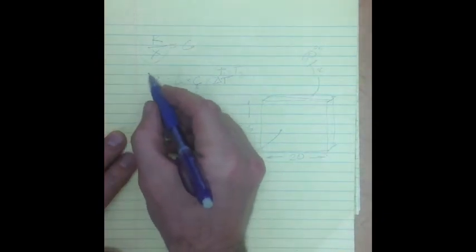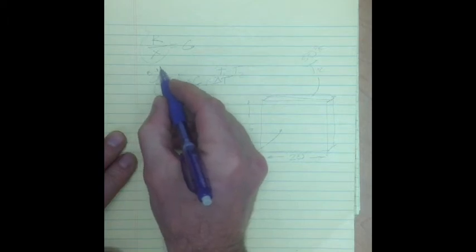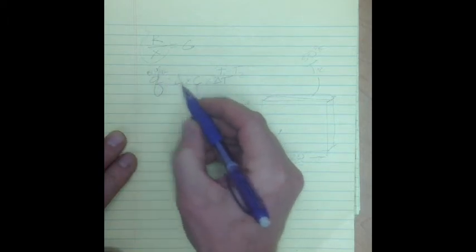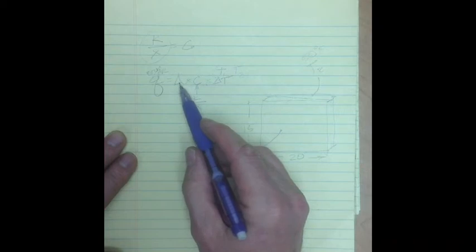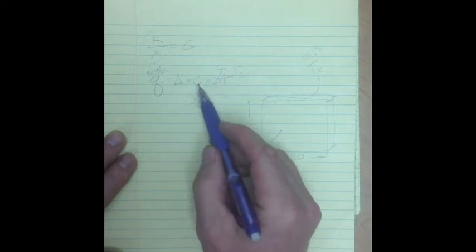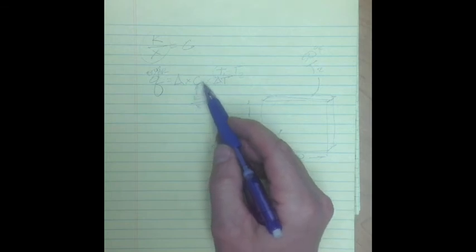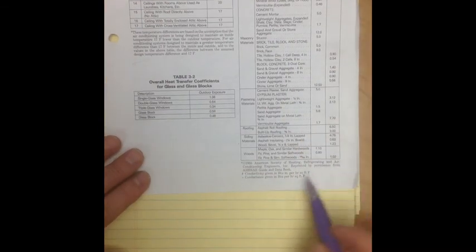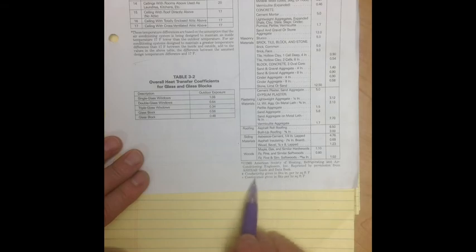Q, which by the way is in units of BTUs per hour, equals the area, foot times foot, times whatever the heat transfer coefficient is, times the difference in temperature from one side of the wall to the other side of the wall.